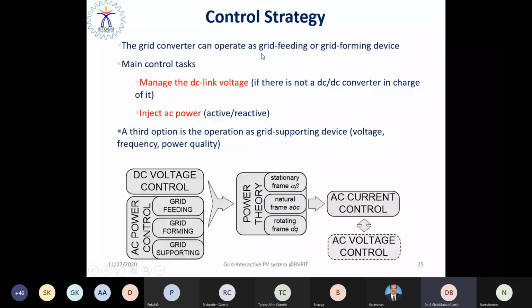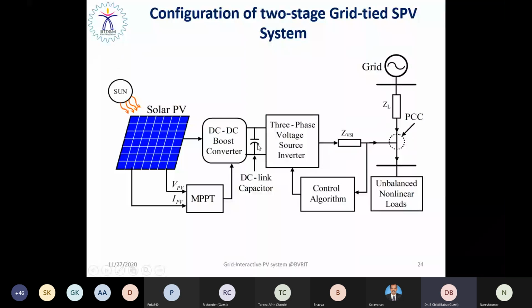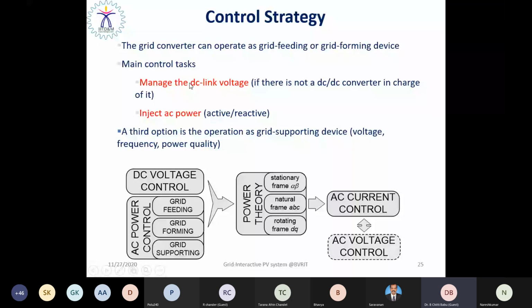The main control task is to manage the DC link voltage. The DC link voltage basically balances the power flow between the solar PV and the utility grid. So the DC link voltage has to be maintained constant to transfer the power from the solar PV to the utility grid. It has to be stabilized at any cost, and it has to inject controllable active as well as reactive power to the utility grid.